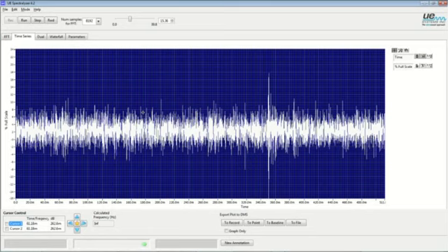the easiest way to say would be we are characteristically going to have this band of white noise across the time analyzer. That's partially the instrument plus what we may be recording. These spikes that we see deviating from that center baseline are going to be representative of discharges of electrical energy, which is what you would have in both an arcing and a tracking event.